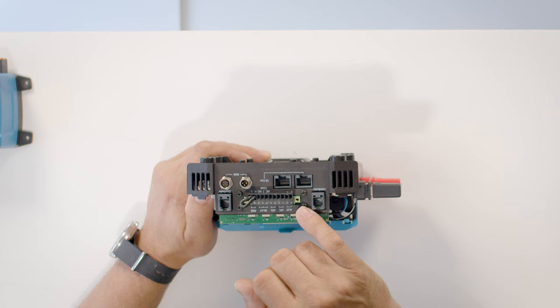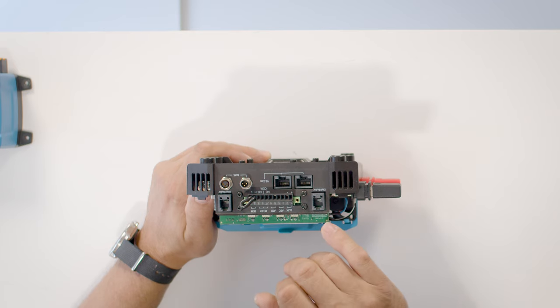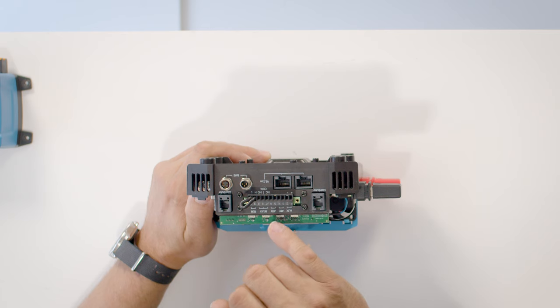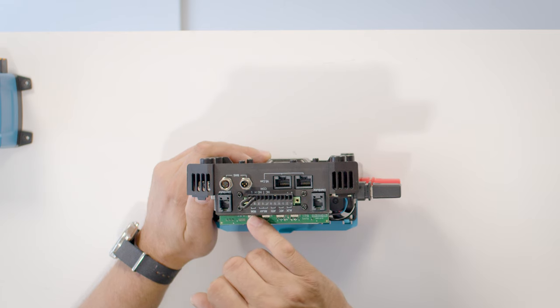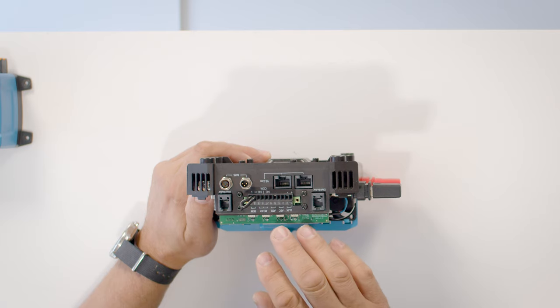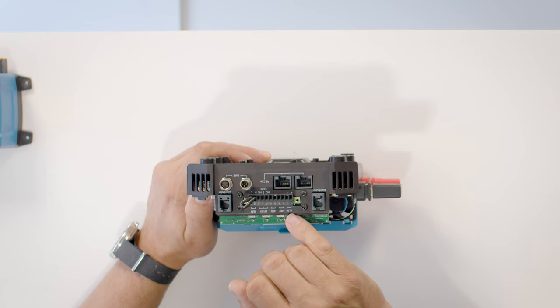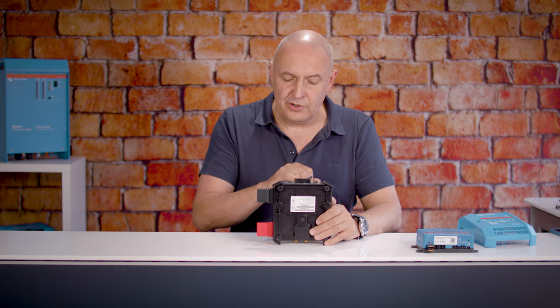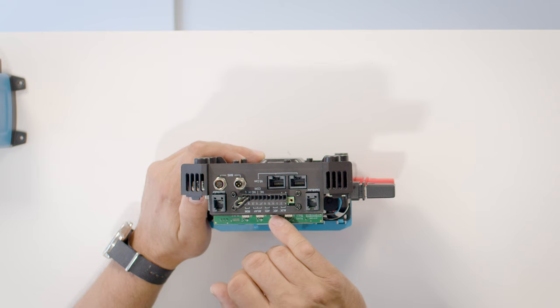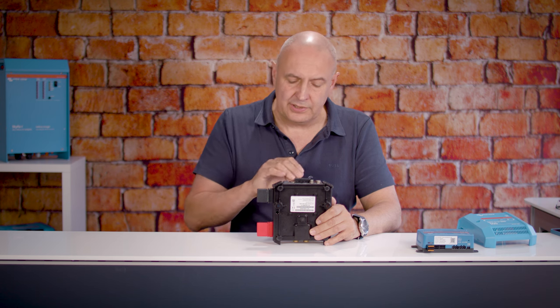So finally, we'll have a look at these terminal blocks here. We've got AUX, ATC, ATD, relay, and remote. And I'm just going to quickly run through what those all do. The AUX is a locally sourced DC power supply that you can use through these volt-free contacts, ATC, ATD, and relay. The ATC is allowed to charge, and this relay opens prior to the main protection contactor opening.